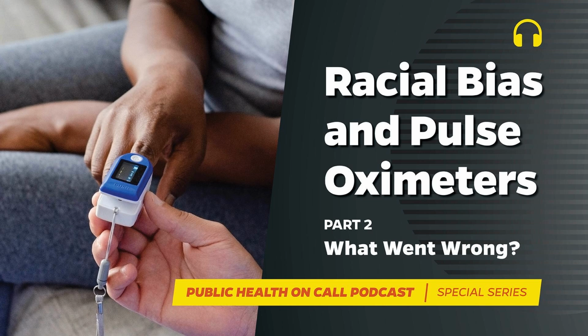Today, pulse oximeters are cleared under what's called the 510(k) review process. It's a pathway that requires that manufacturers prove that their device is substantially similar to another marketed device, cleared under similar rules. This pathway has many advantages for bringing devices quickly to market. That is exactly its goal. But there's a weakness too. If the initial device is flawed, then other devices can be brought to market with the same flaws.